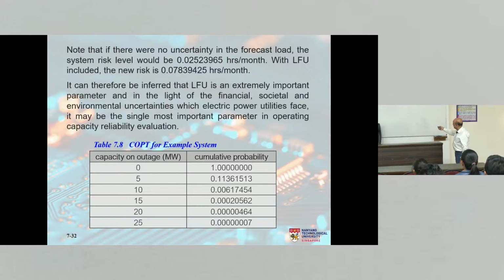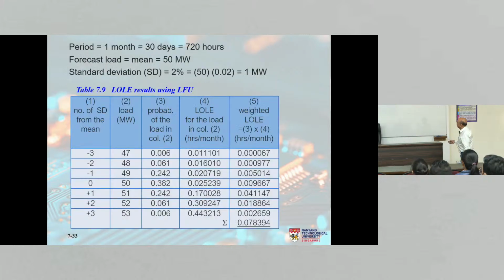Now, this is the COPT, and again, I'm not including any stages after this because it's already 10 to the power minus 8 or something like that, right? So for the peak load to be 50 megawatt, these are the calculations. The risk is 0.025239. That's the risk. You can calculate using the cumulative probability table, okay? Now what I need to do is calculate the risk for 49 megawatt load, 48 megawatt, 47. Why? Because the standard deviation is 1 megawatt. So I'm going minus 3 standard deviations, I'm going plus 3 standard deviations. So I have to do the calculation 1, 2, 3, 4, 5, 6 more times.